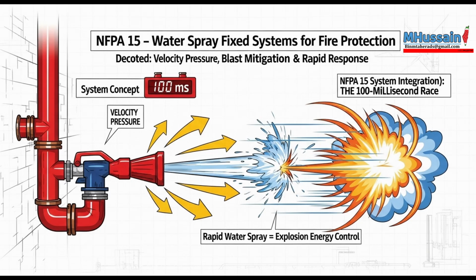First, certified judgment, especially needing that RPE sign-off for things like structural connections or alternative analyses. Right. Second, meticulous installation, validated by things like welding procedure qualifications and getting that piping slope absolutely perfect, especially for UHS. And third, mastering the complex fluid dynamics, particularly the non-negotiable accurate inclusion of the velocity pressure correction, PV, in every single calculation. You just can't fudge the numbers or rely on big safety factors to cover sloppy hydraulic math when you're dealing with these kinds of deluge systems.